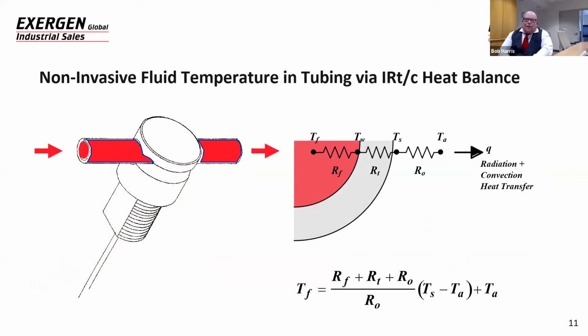So here's another example where we have on the left an IRTC going into a special tubing clip that's measuring the fluid temperature inside that tube. As I said earlier, everything correlates. You have the fluid temperature, and RF is the thermal resistance of the fluid. RT is the thermal resistance of the tubing. And TW is the temperature of the inner wall and the outer wall of the tubing. So everything correlates. When the TF increases, the temperature of the surface increases. So by calibrating the IRTC, and to calibrate you just turn a potentiometer, that'll give you the output and display the temperature of the fluid. It's pretty simple, much like the algorithms that we have in the temporal scanner, and it's very widely used for a lot of the medical OEMs.